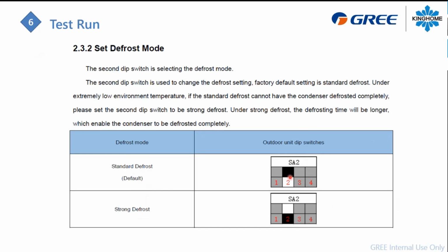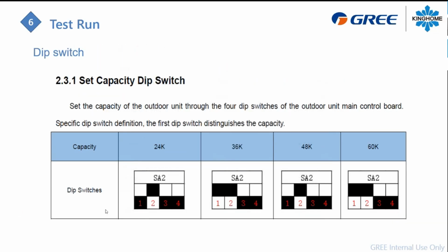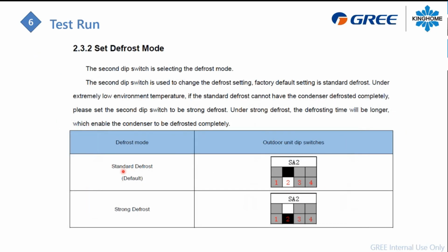Dip switch number 2. This is the same block, but we are moving to dip switch number 2. It's your defrost mode switch. If we go back here, you can see by default it's on, for a 3-ton or 5-ton. On means standard defrost, so the algorithm of the unit will use standard defrost, depending on time, temperature, and all the factors that make the defrost happen. So you let it on.